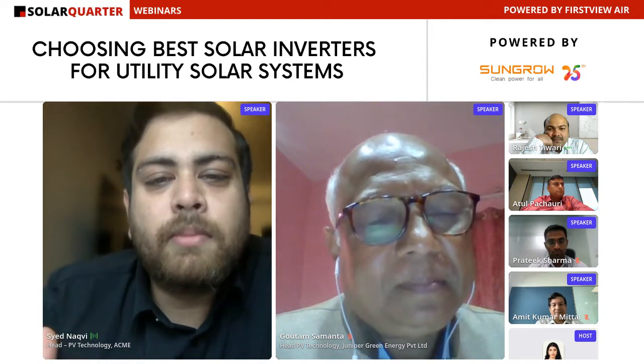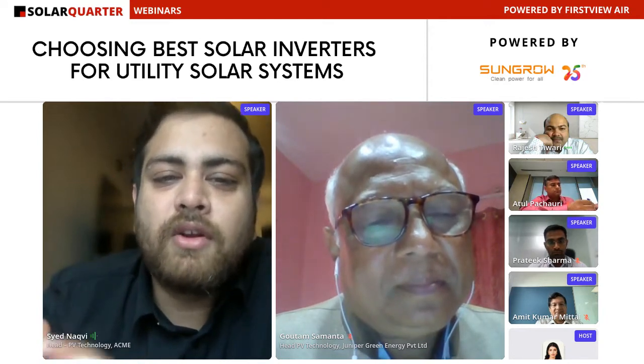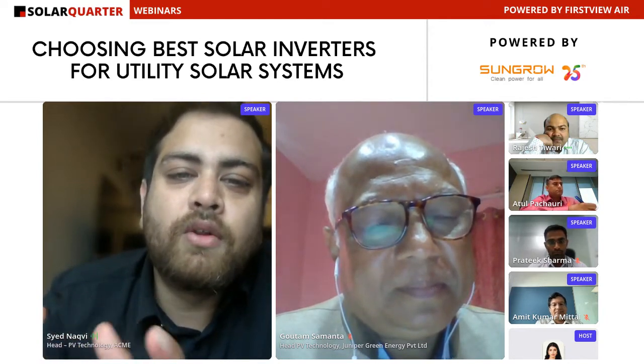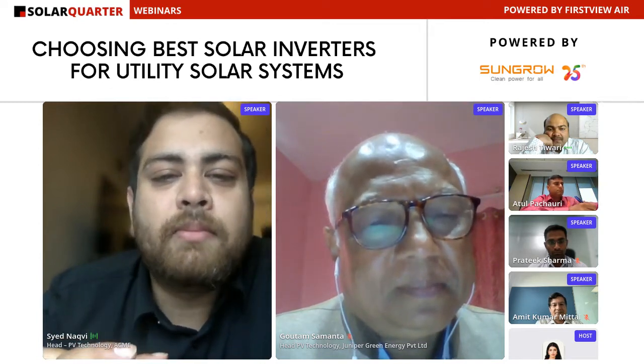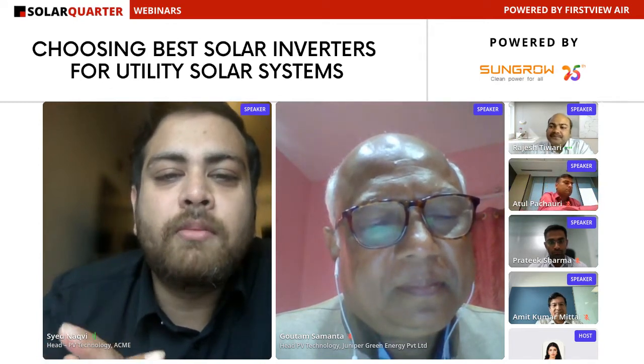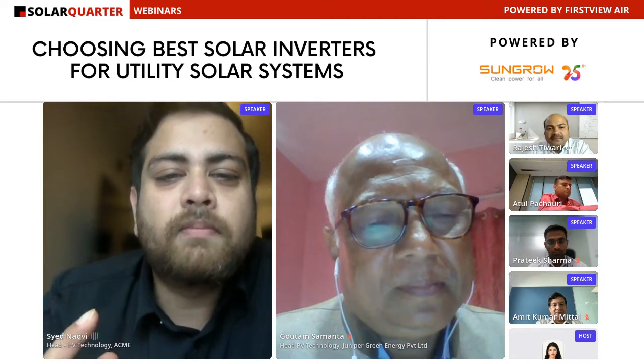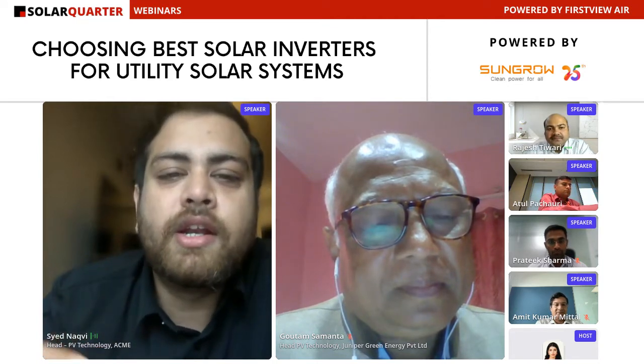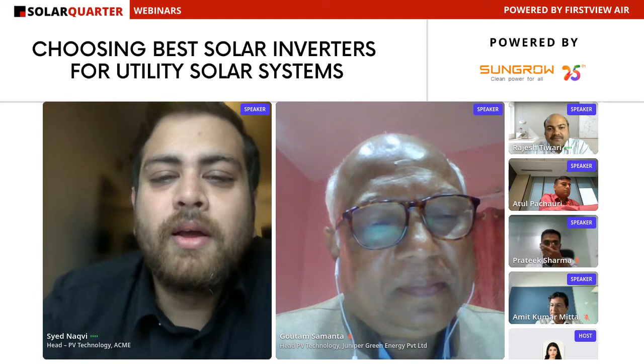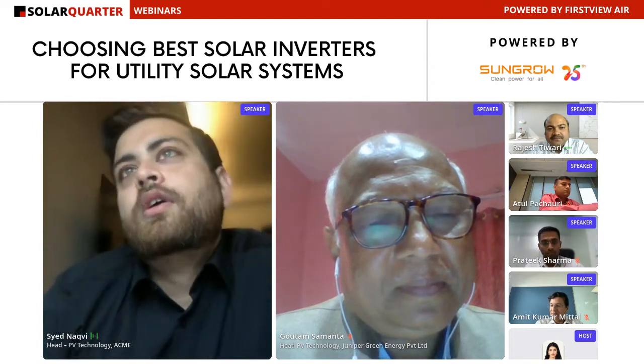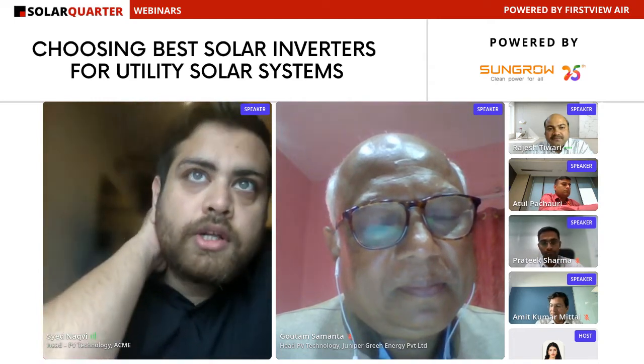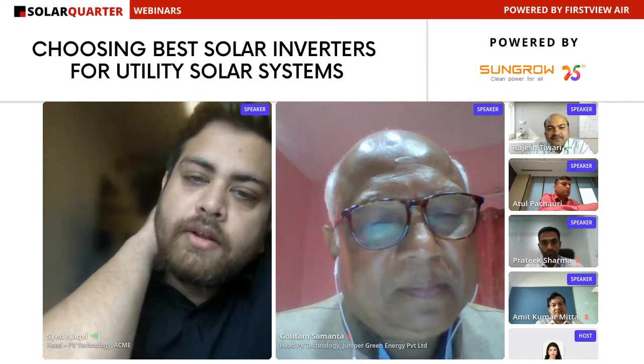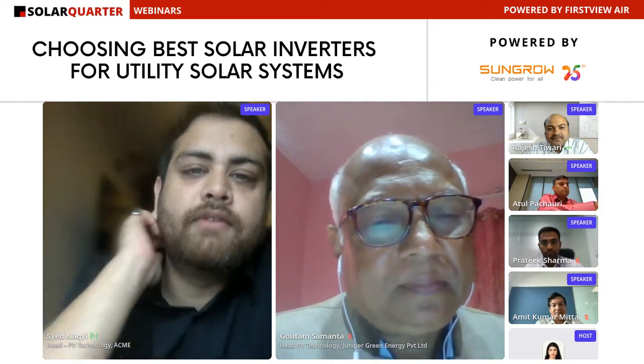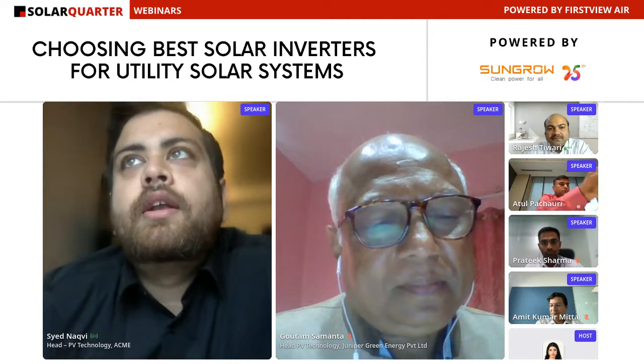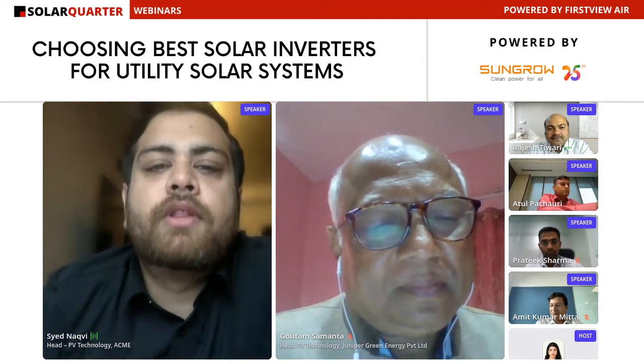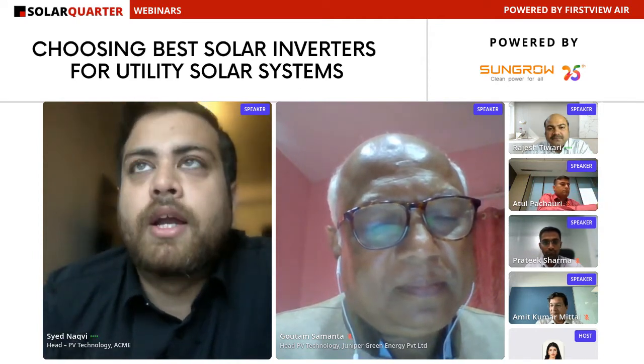As we go to bigger module sizes, we are constricting ourselves on the number of modules in a string. For M10, it's very difficult to connect 29-module strings because you'd go over 1500 volts during certain times of the year, which the module guys would not allow. So I would like to see more research and more products coming up, especially on the central and string side, with higher voltages compatible with the bigger module sizes available in the market.